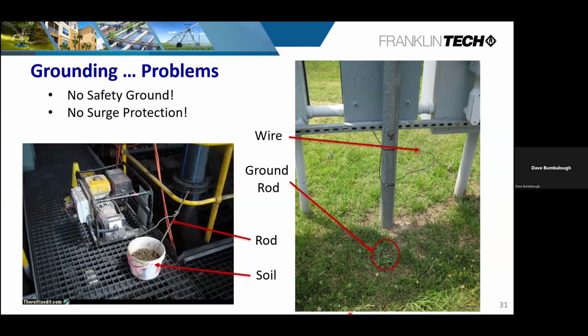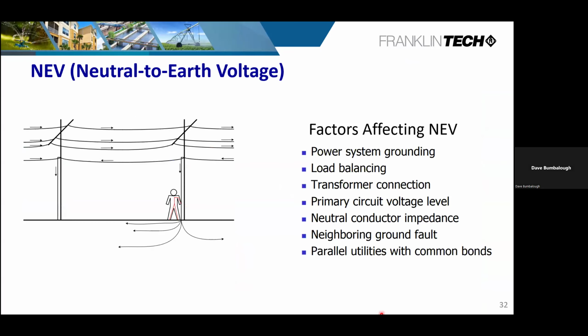Kind of keep you awake since we're almost in the final run here, but it's all about interpretation, all about checking and making sure things are where they need to be. Now, granted, as a water well professional, you wouldn't necessarily look for this issue here. That has nothing to do with my water well system. But in reality, inside this panel, there was surge protection that's supposed to be protecting your equipment, but it's doing a poor job of it because something had happened here. Okay. And yes, it may be outside your realm, but we need to be educated enough to identify this type of thing so we can bring it to their attention. Well, this is why the equipment failed, because the protection couldn't do its job. Okay. Because it wasn't even attached. So things like this can pop up.